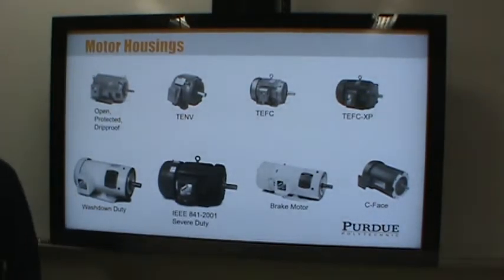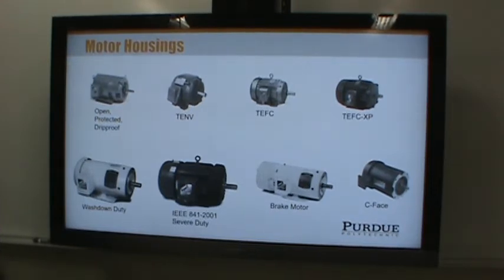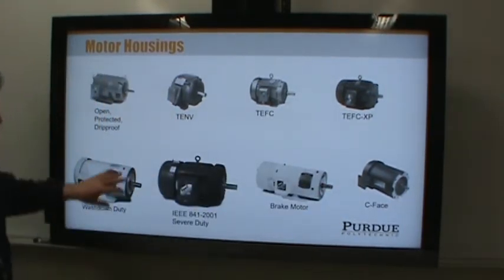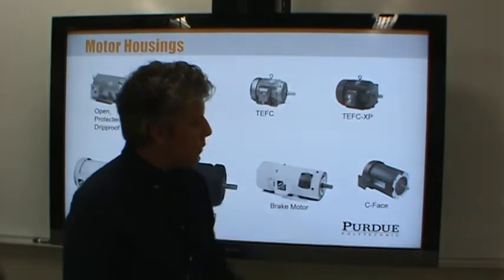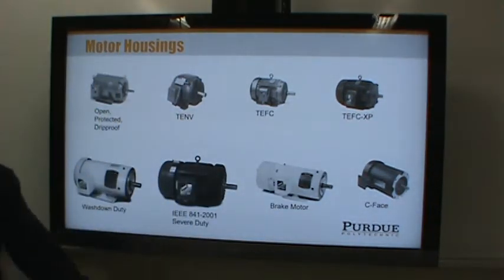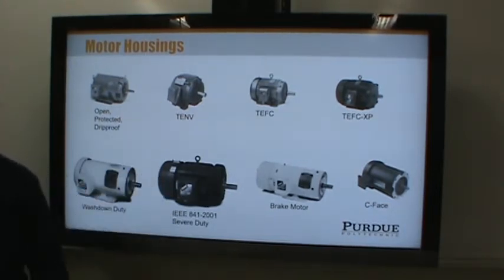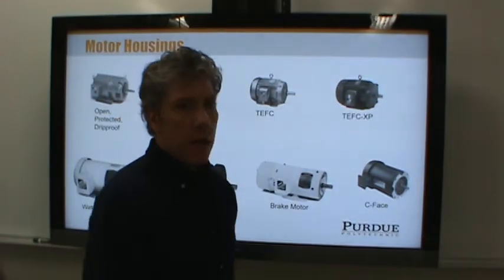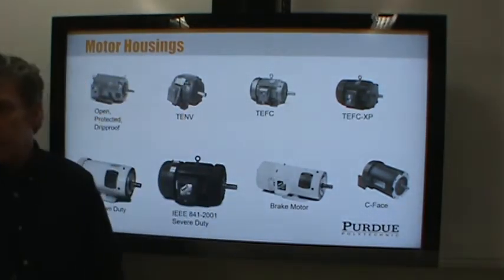Motor housings in industry are more likely to be three-phase than single-phase, but some cross over to single-phase. The faces of these motors are typically standardized, and dimensions like the distance between the shaft and the feet of the motor are also standardized, so you can buy a motor from one manufacturer and replace it with one from another. The details of quality, efficiency, and reliability vary by manufacturer.